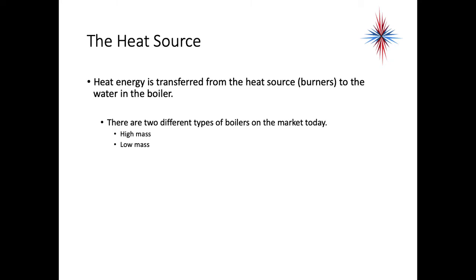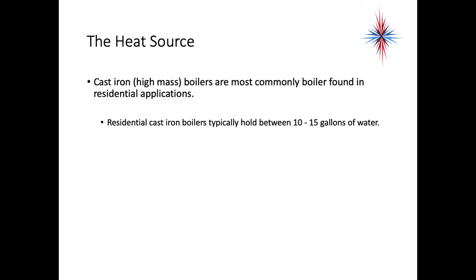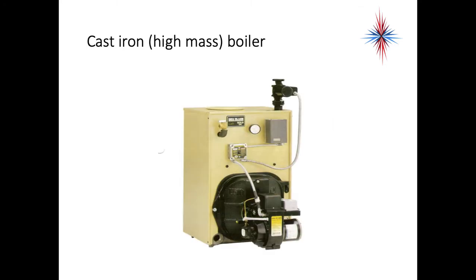Heat energy is transferred from the heat source — the burners — to the water in the boilers. We have two types of boilers on the market today: high-mass and low-mass. The cast-iron boiler is a high-mass boiler and the most commonly found in residential applications, though that's changing. Residential cast-iron boilers typically hold between 10 to 15 gallons of water. Weil-McLain is a pretty good brand that you'll see around a lot.